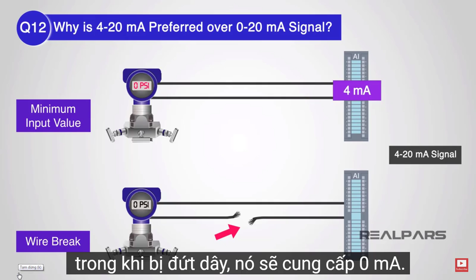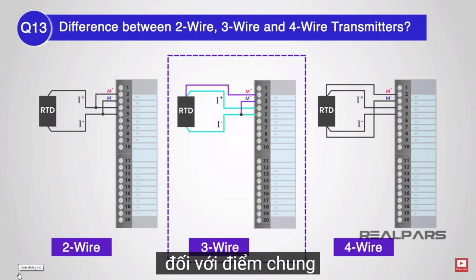Question 13: What's the difference between 2-wire, 3-wire, and 4-wire transmitters? Answer: in a 2-wire transmitter, power and signal share the same cable. In a 3-wire transmitter, the data signal and power are referenced to a common ground. In a 4-wire transmitter, two wires carry power and two wires carry the signal.